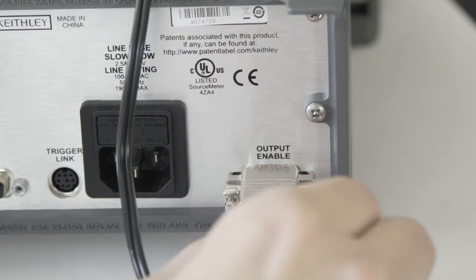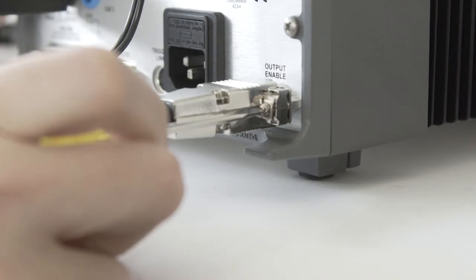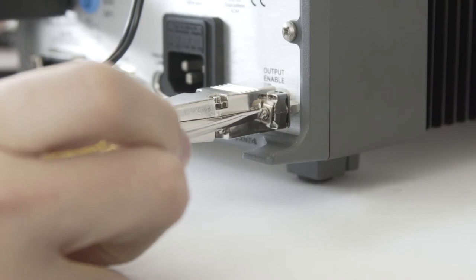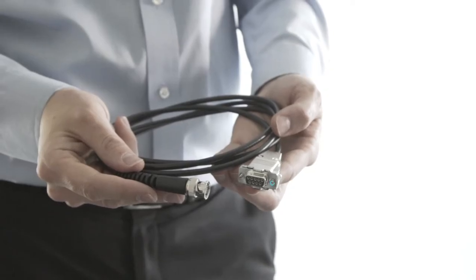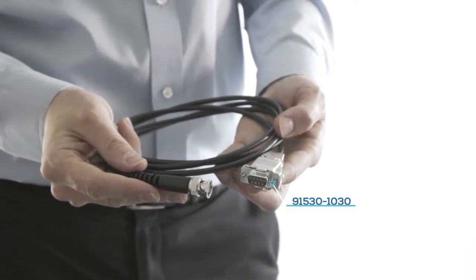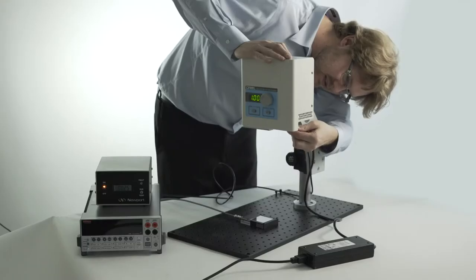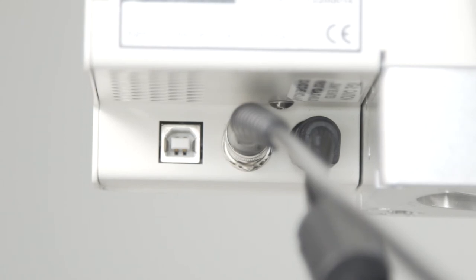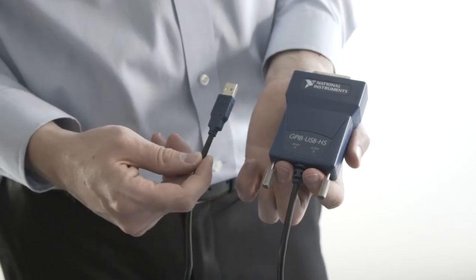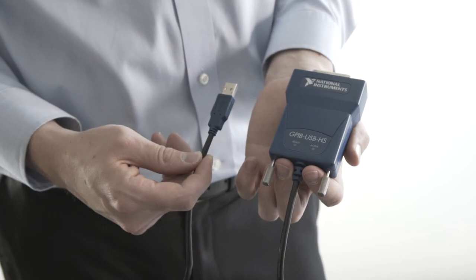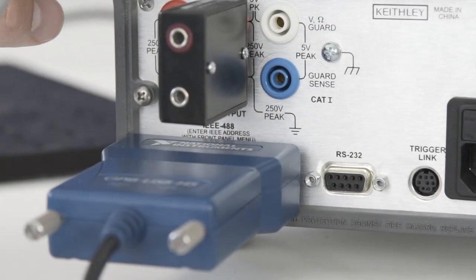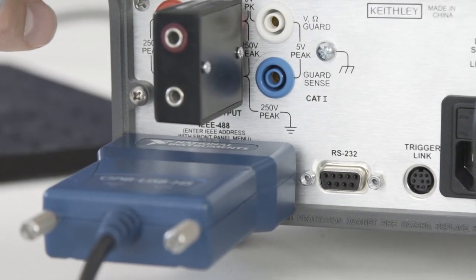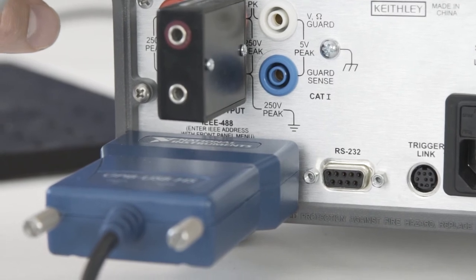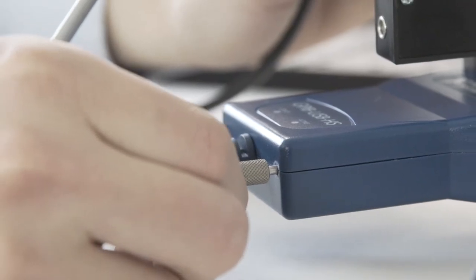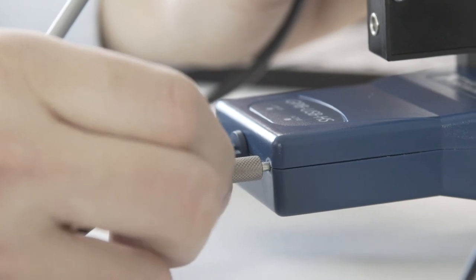The port labeled Output Enable is for shutter control of the simulator. The BNC end of cable 91530-1030 connects directly to the MiniSol, which will turn on and off the LEDs. Last, the National Instruments GPIB to USB cable is secured to the GPIB port on the back panel with the USB end connected to the computer. Ensure that the GPIB side is securely seated to the port.